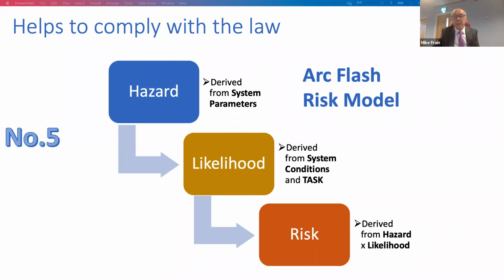And from my guide, I explain a 4P approach to eliminate or control the risk at that point. When we have the means to evaluate the hazards in a workplace, we must take advantage, in my view. As said earlier, it's a matter of a few amperes that can be the difference between an arcing fault being cleared quickly and harmlessly and a situation that results in catastrophic damage, losses and severe personal injury, just for the sake of a few amps.